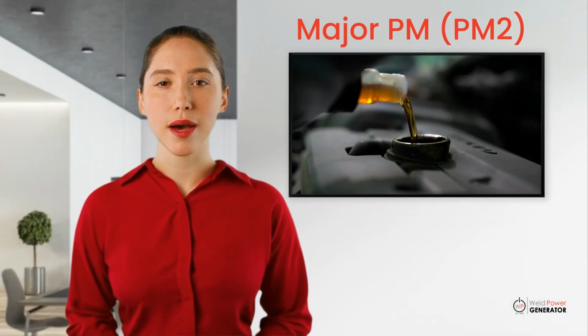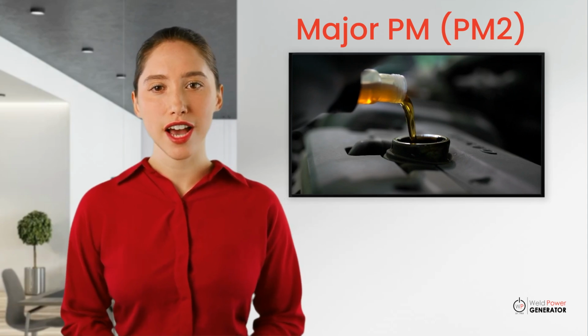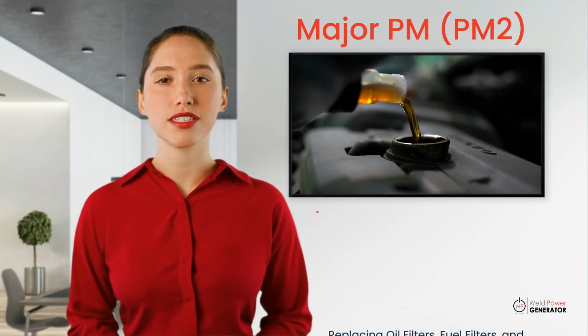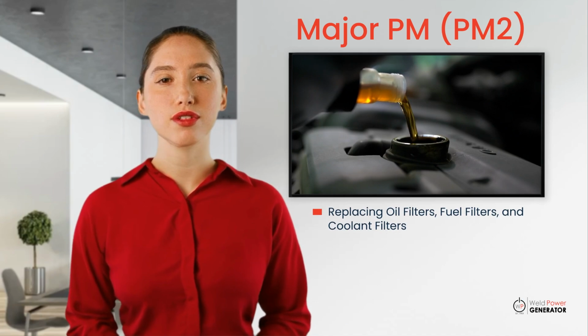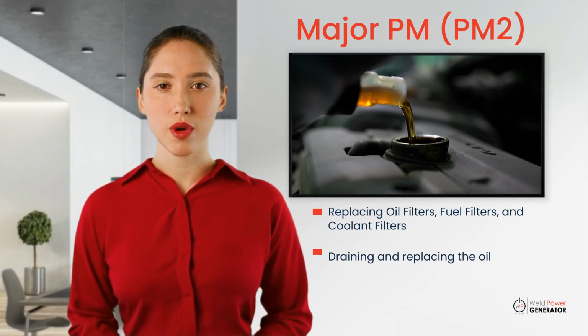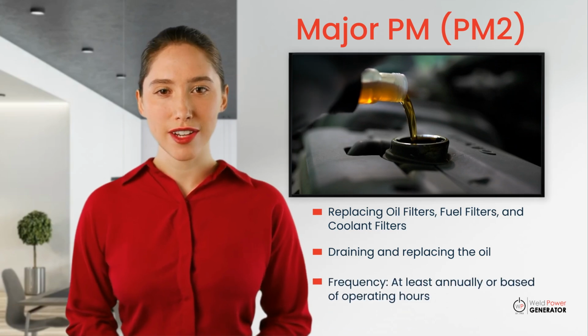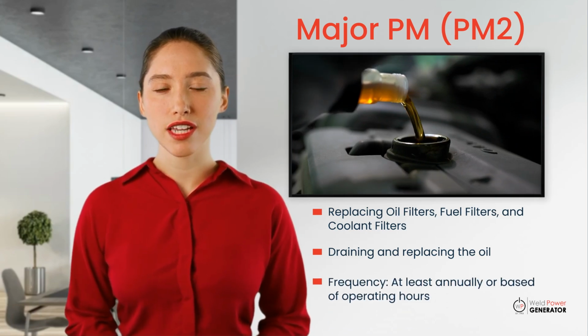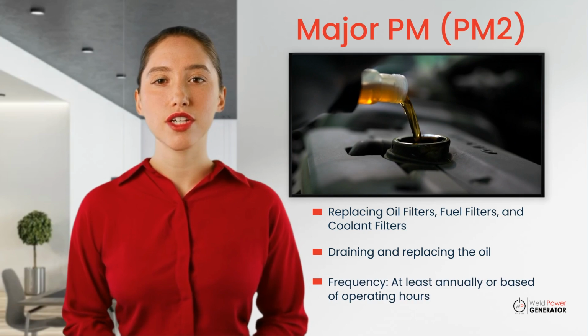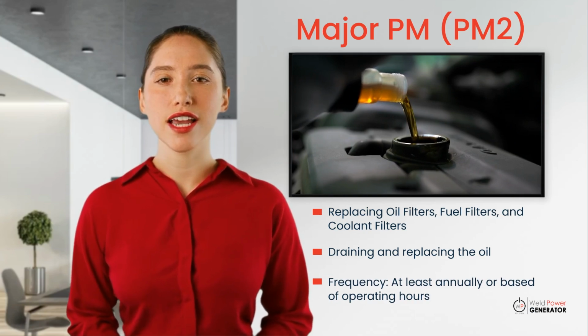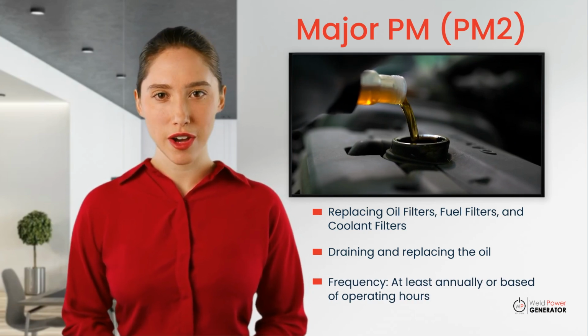A major PM or PM2 includes everything covered in a minor PM, plus changing the oil filters, fuel filters, coolant filters, and fully replacing the oil. Typically conducted annually or based on hours of operation, major PM ensures that critical components are in working condition and reduces the risk of generator failure during an outage.